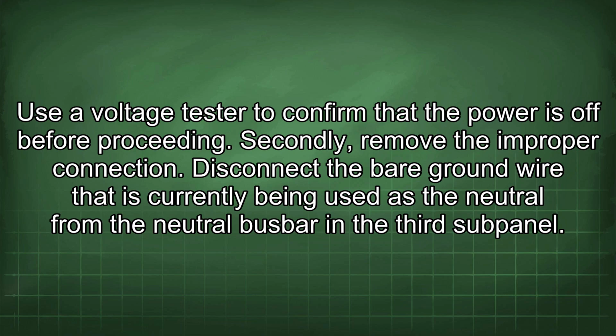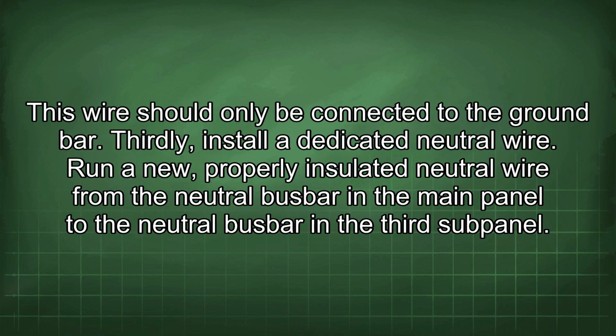Secondly, remove the improper connection. Disconnect the bare ground wire that is currently being used as the neutral from the neutral busbar in the third subpanel. This wire should only be connected to the ground bar. Thirdly, install a dedicated neutral wire.